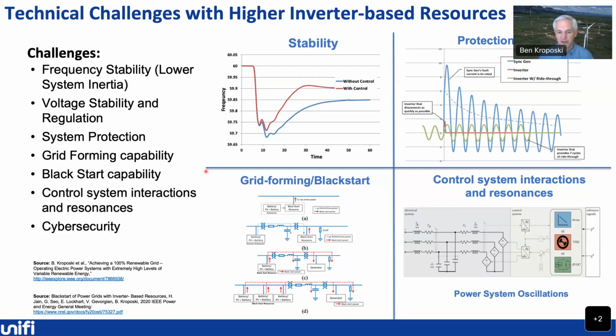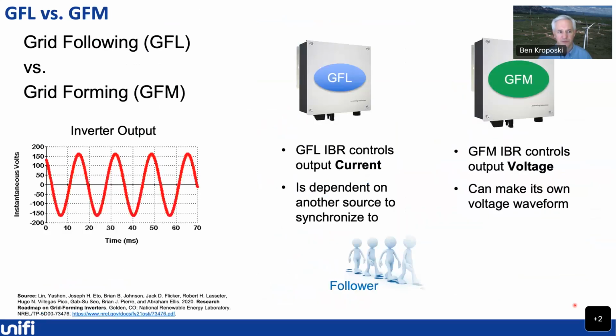And then as we start to deploy more and more of these inverter-based resources, the control algorithms inside them potentially can be causing oscillations as they are reacting to disturbances on the grid. And we want to make sure that we're building in functions inside the control algorithms that can dampen some of these system-wide oscillations that may be occurring. So again, a variety of these technical challenges with inverter-based resources.